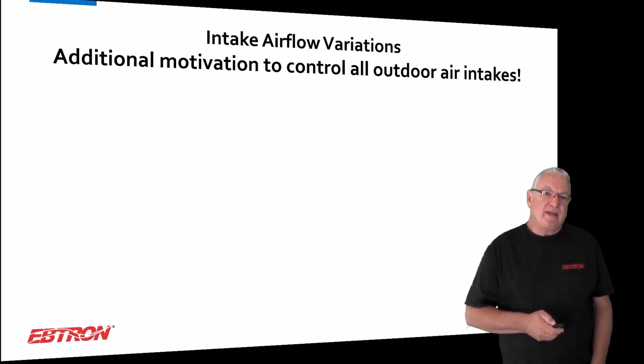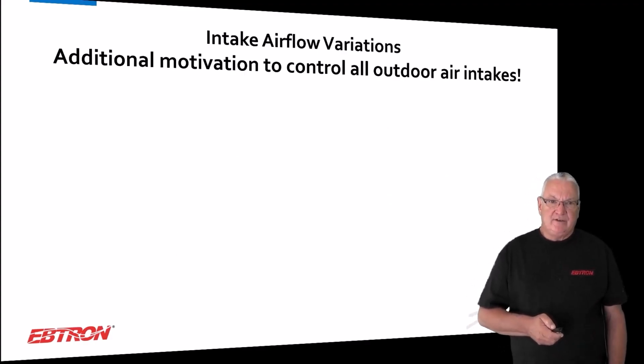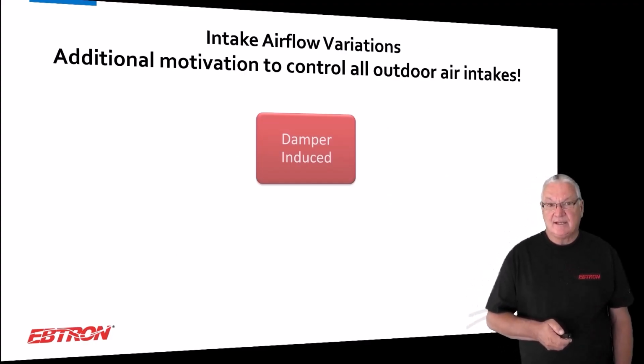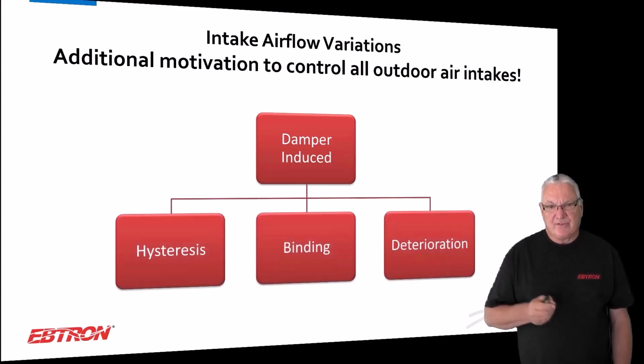When we take a look at air handling units again, or anything that depends on dampers, I mean, dampers are oversized valves, and even the best ones aren't the greatest control valve. And so the problems you have are three.